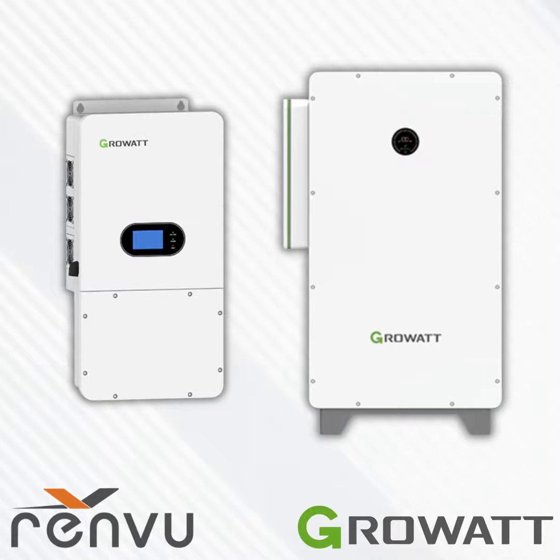This is an HU model shown. I'm sorry, this is an H or HU model. The U stands for UPS. So in this application, this is completely on grid with no backup load. And that's okay. You can use the H or the HU model. It has PV connection directly into the inverter, energy storage directly to the inverter, and a grid port connected to it. The only extra piece of equipment that we need if we want to do any kind of grid interaction, so export limitation, as an example, is an external meter that we can supply. And then there's no load on this.